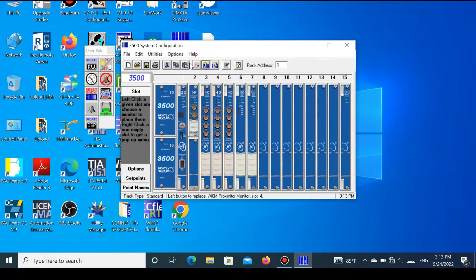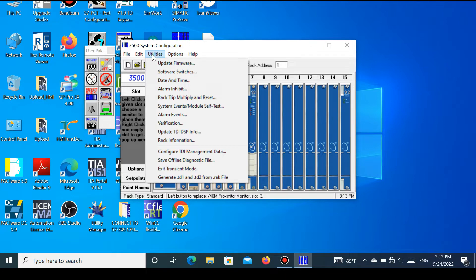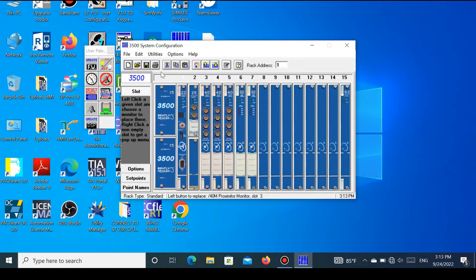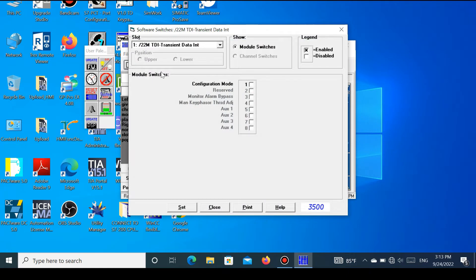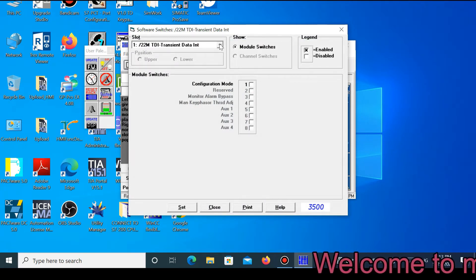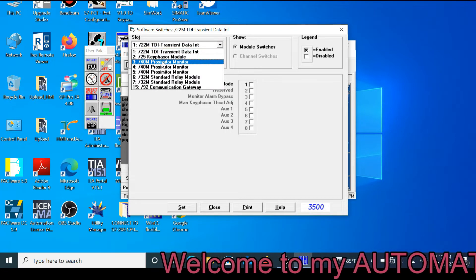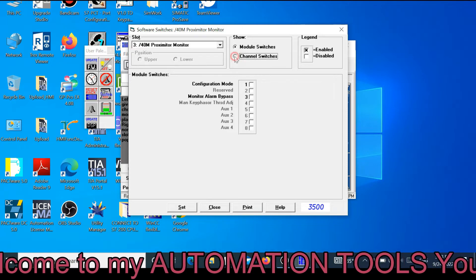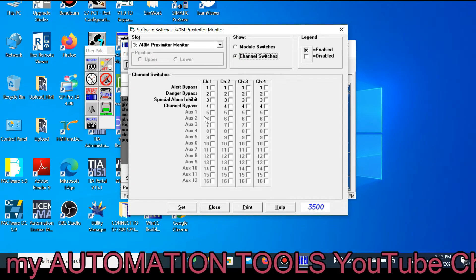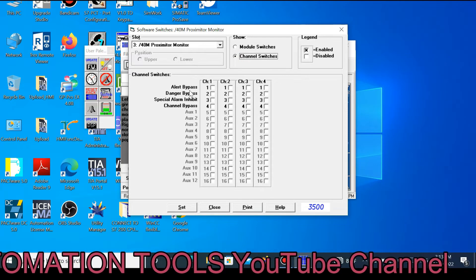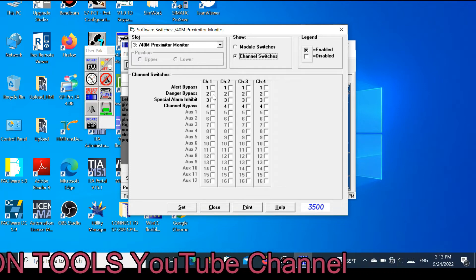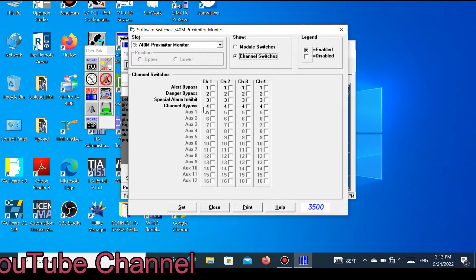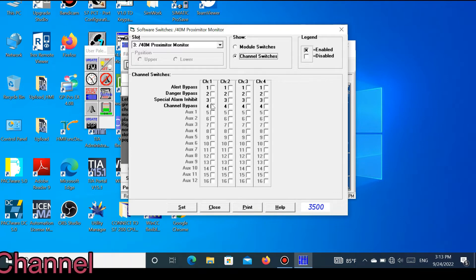Go to the Utility button, then go to Software Switches. Here we can see the slot numbers. Go to the desired slot number and select which channel you want to bypass. Go to the desired monitor and press Channel Switches. Here the bypassing system is shown — one module contains four channels. The options are: Alert Bypass, Danger Bypass, Special Alarm Inhibit, and Channel Bypass.